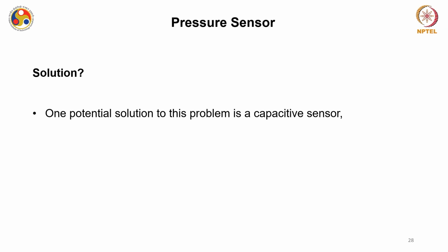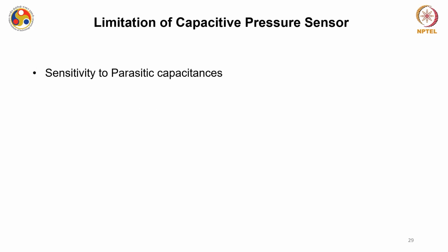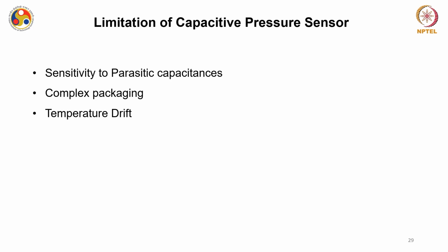However, the capacitive pressure sensor, we have seen, offers some answer, particularly when you are dealing with low pressures, but not all. There are various limitations associated with the capacitive pressure sensor. It is sensitive to parasitic capacitances, which can arise because of interference from outside. These devices are very complex to package because you again have the moving diaphragm, and electronic-grade packaging is very difficult, similar to other MEMS sensors. Then you have temperature drift effects in capacitive pressure sensors, and because of the very thin diaphragm, the device is very fragile.